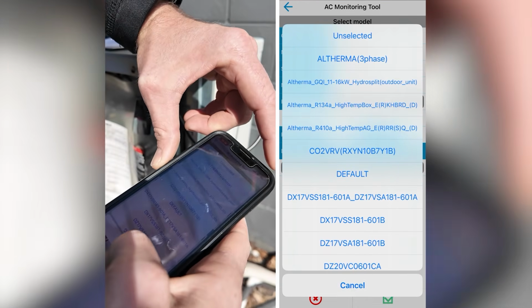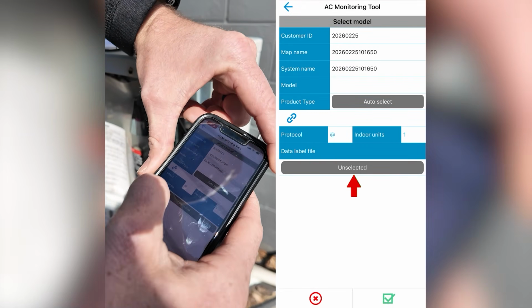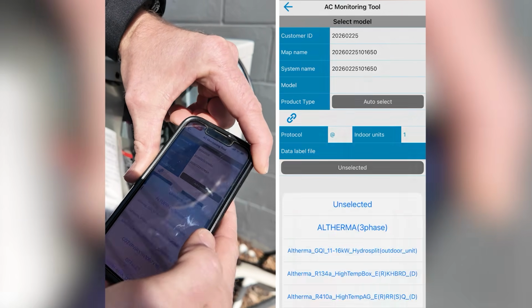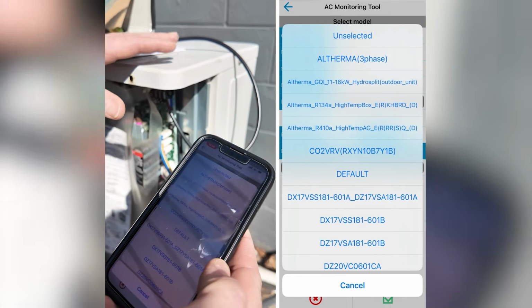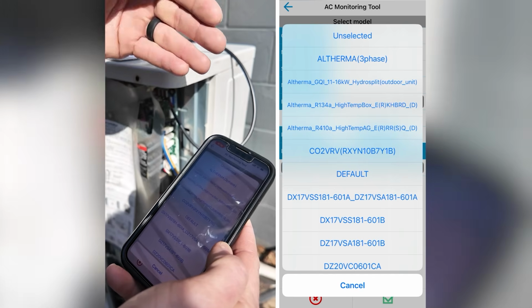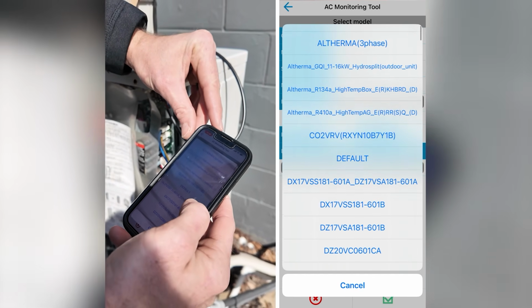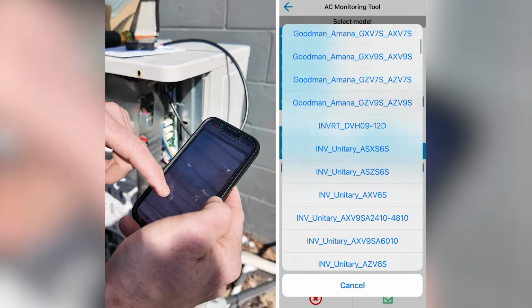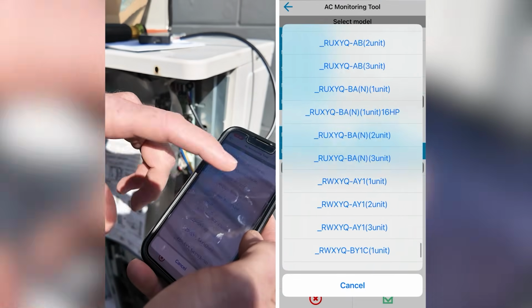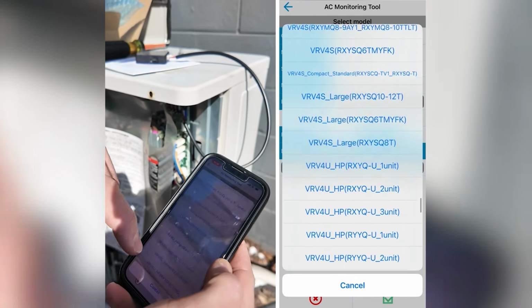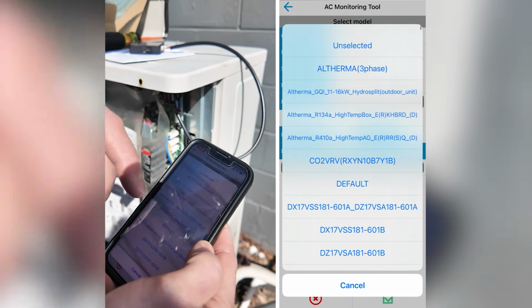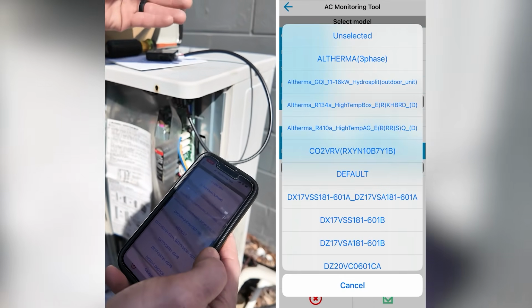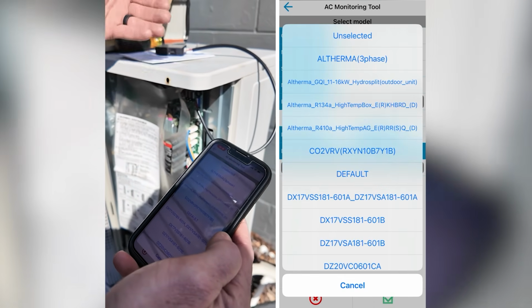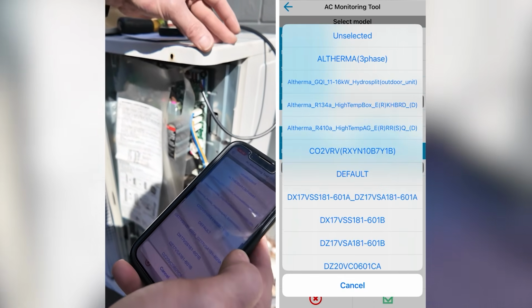At the bottom here, where it says unselected, I have to pick the data label file manually. Right? It has found the indoor units and how many are connected. Now I have to tell it what I am hooked to. If you incorrectly select something from this very, very long list, it'll put the discharge temperature, the suction pressure, all of those numbers in the wrong places and wrong categories, so that when you go to troubleshoot and look at the data, none of it is going to make any sense.